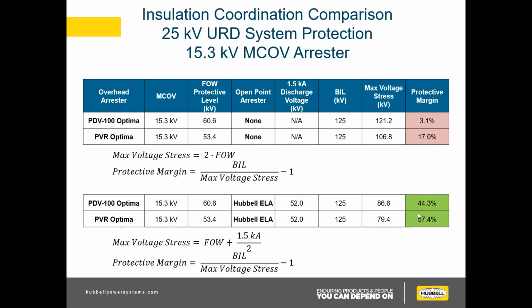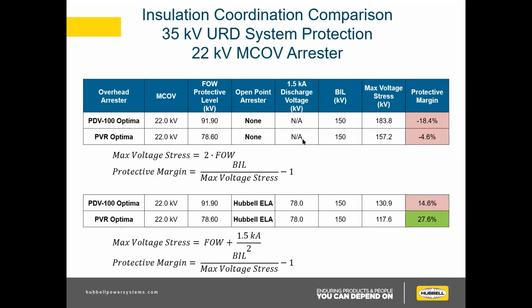And so simply adding an elbow arrestor in that pad mount box, your margins are healthy again. Everything's protected and it should be fine with the IEEE guidance. So 15.3 will move up again to a 22 kV. So this is where you really have to be careful. You're terrible on margins with no elbow arrestor.